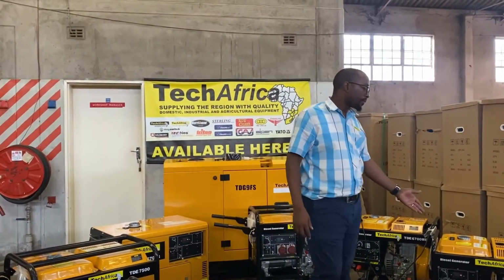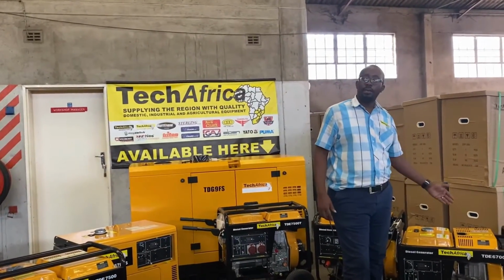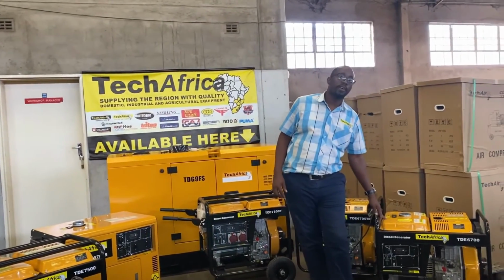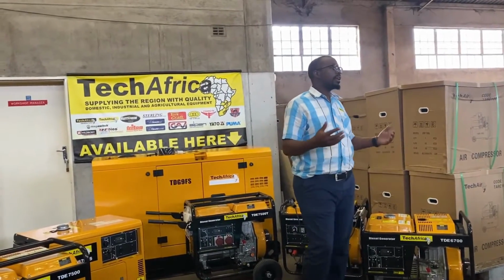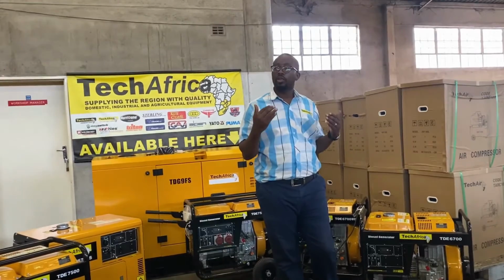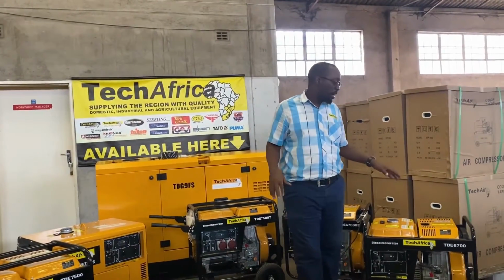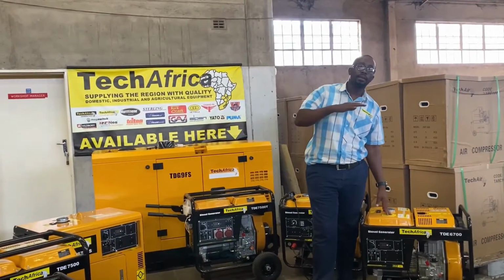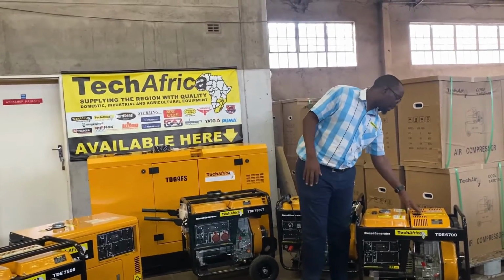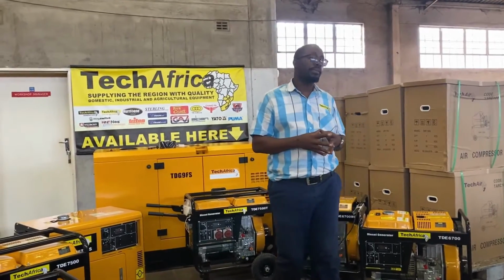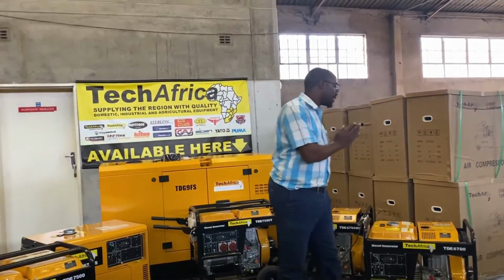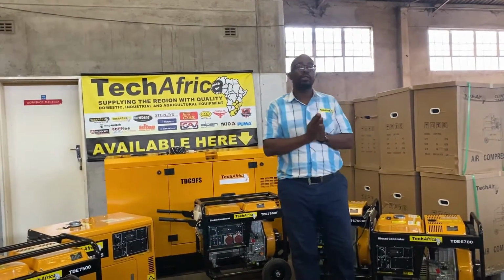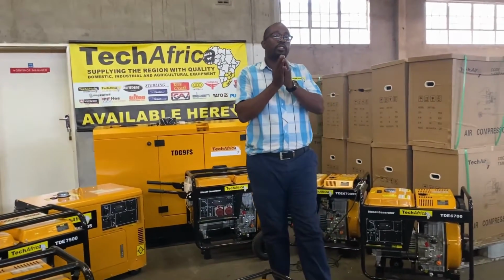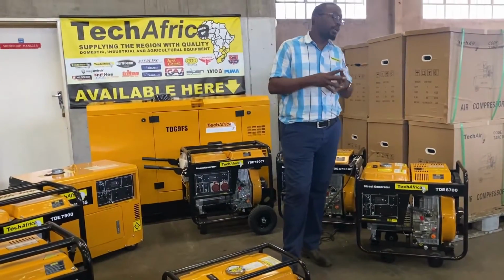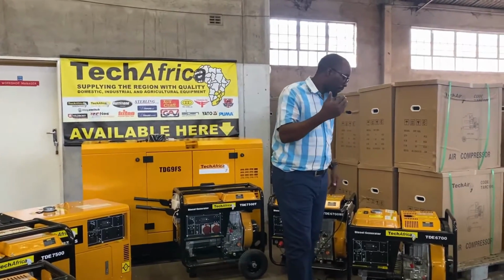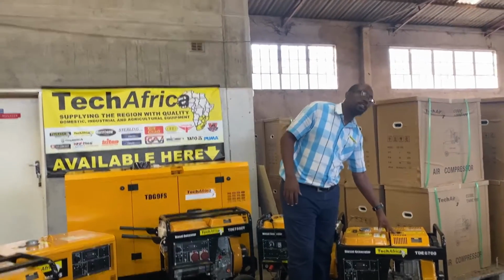We've got the TDE 6700, which is rated at 4.5 kVA, maximum 5 kVA. It's got a total amperage of 20.5 amps. We usually encourage customers to run these generators at up to about 80% load, so that you can leave a 20% safety margin for your generator to be operating under normal conditions. So ladies and gentlemen, out of the 20.5 amps, you need to run that generator at about 80% load. Bear in mind that will be around 16 to 17 amps, leaving at least 3.5 amps as a safety gap for you in order not to overload the unit.